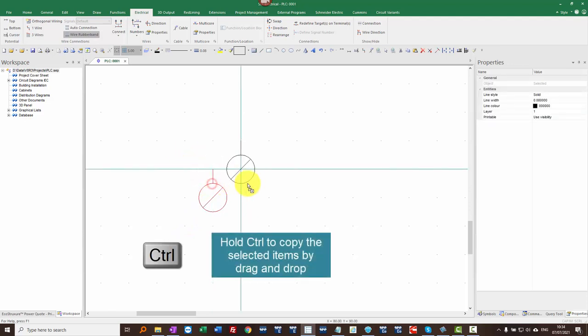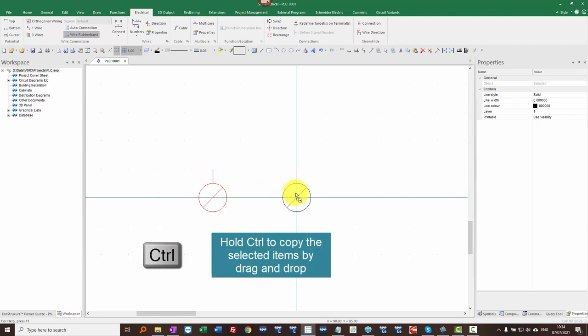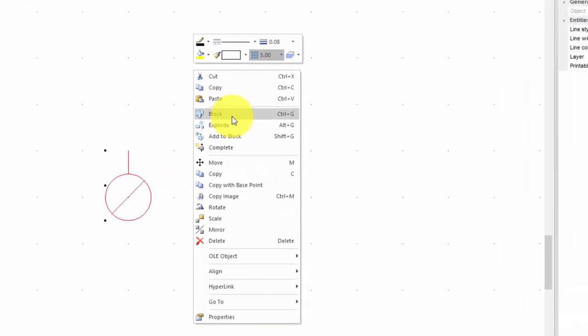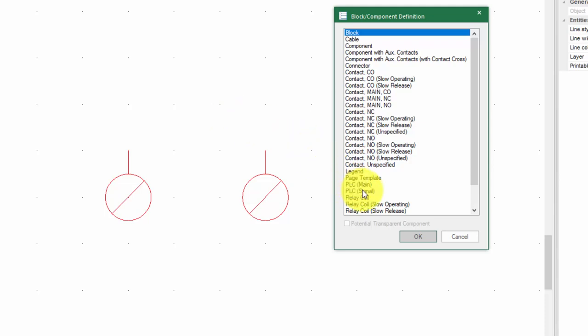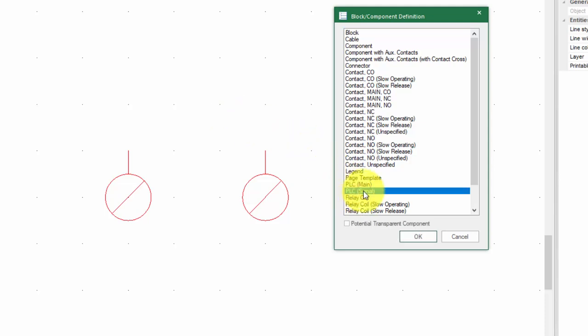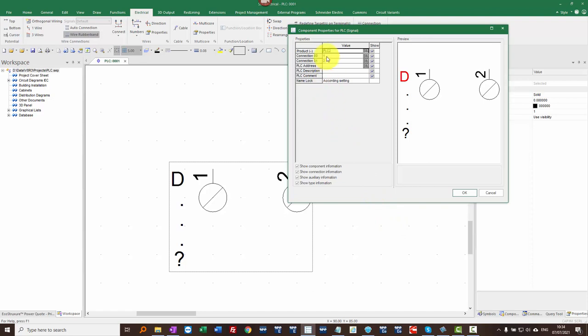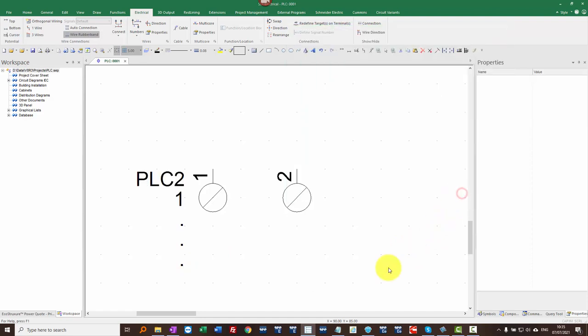I'm going to window around that and hold down Ctrl, drag that across to the right, putting a bit of a gap between the two connection points. So it's going to be an analog input at the bottom of the page with two connection points. That's all I need for the graphics. I'm going to right-click, once I've selected everything, and choose Block. By choosing Block and setting it as a PLC signal, the software will add the attributes — the text descriptions that are minimal for a PLC signal. I'll click OK, and notice it's added a connection point for each of those lines I've drawn, plus a PLC address — I'm going to set that as number one — a description, a comment, and a cross reference back to the PLC main. I'll click OK and that's fine.